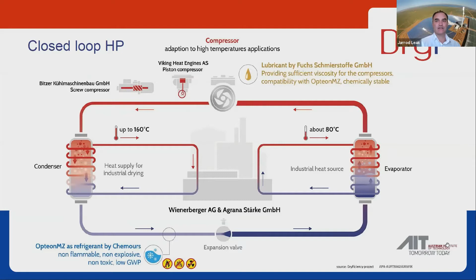As a refrigerant we use a synthetic fluid produced by Chemours, Opteon MZ, or R1336MZZ. It's not flammable, not explosive, non-toxic, and also has a low GWP value, and it was especially developed for high temperature applications.